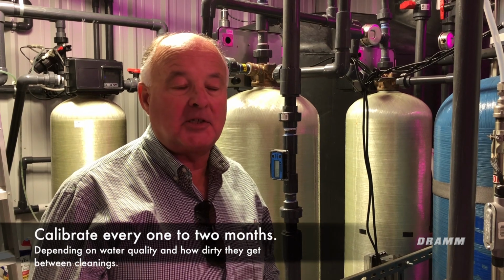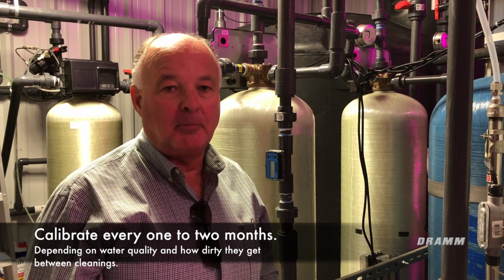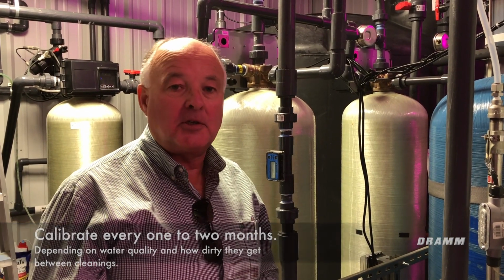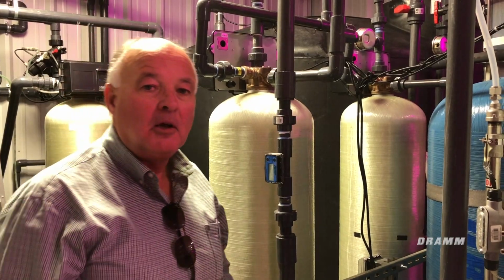We are going to calibrate our ORP probe. An ORP probe is exactly the same as a pH probe. They need to be replaced about once a year. You'll notice that it needs to be replaced when the values drift. But in the meantime, we want to recalibrate it every so often, maybe once a month or once every 2 months, and clean it and put it back in place. So we're going to do a real quick job of that today.